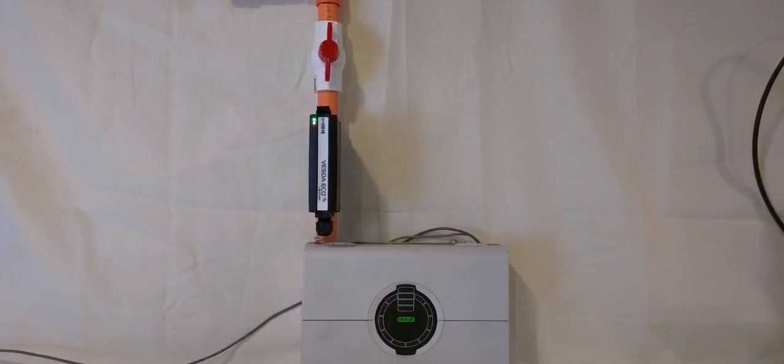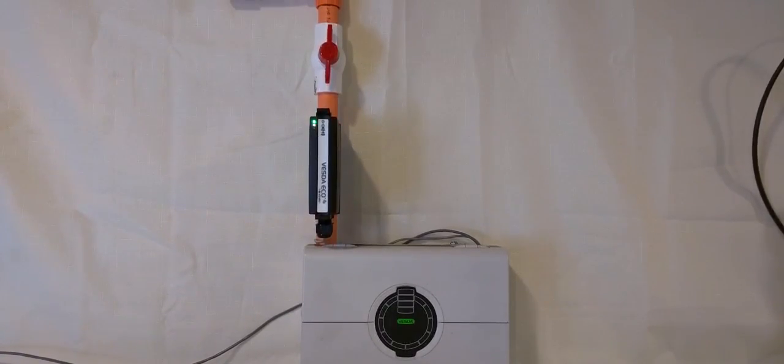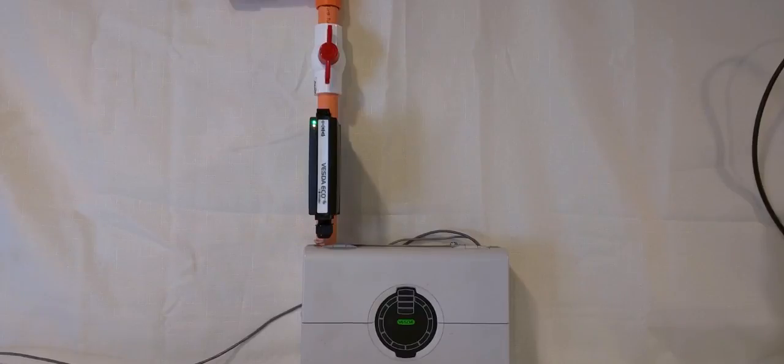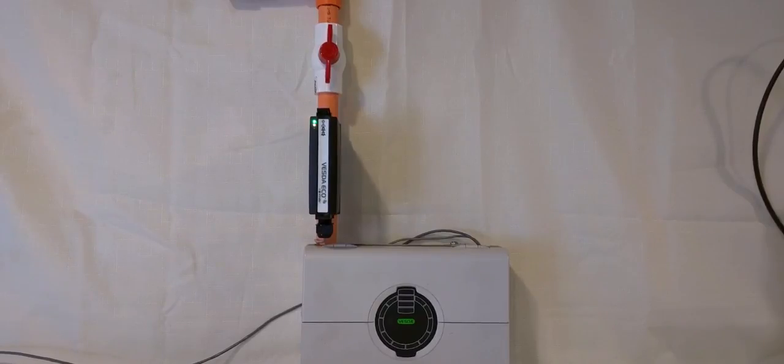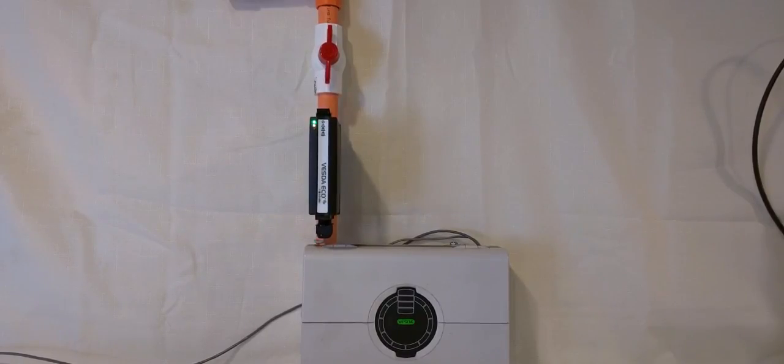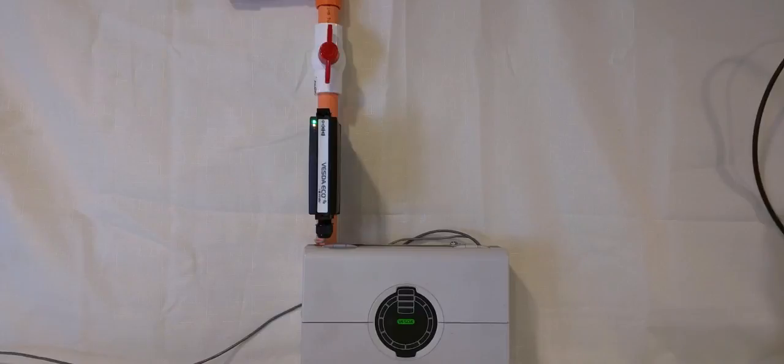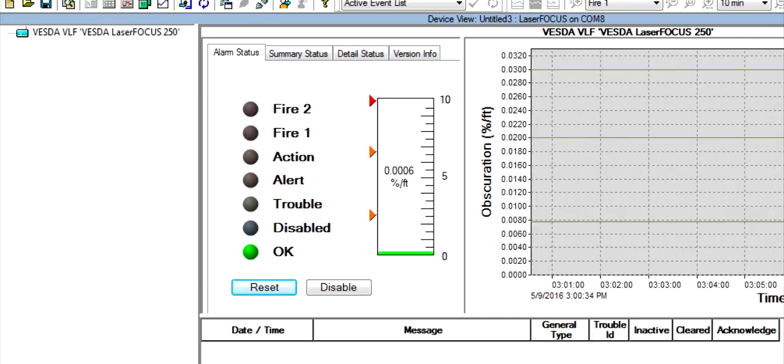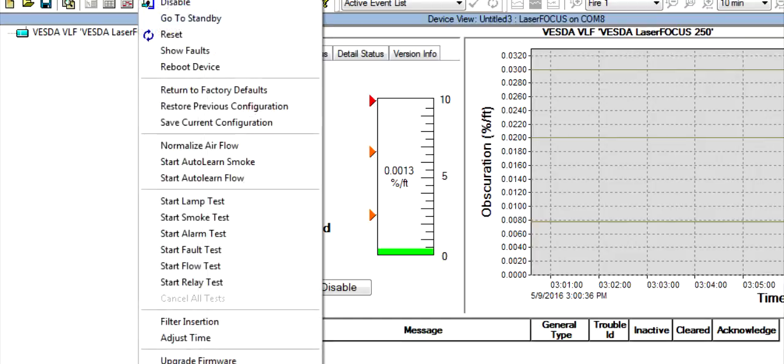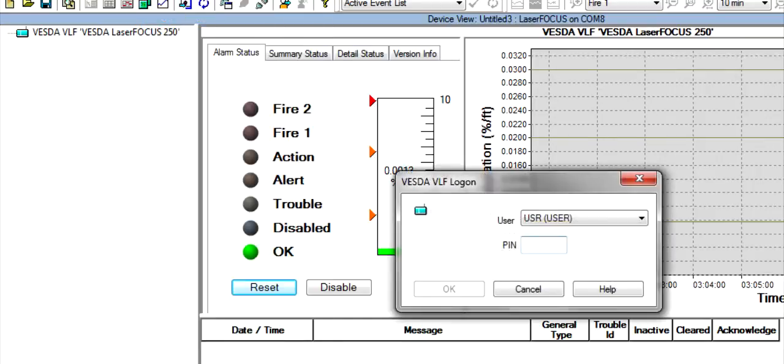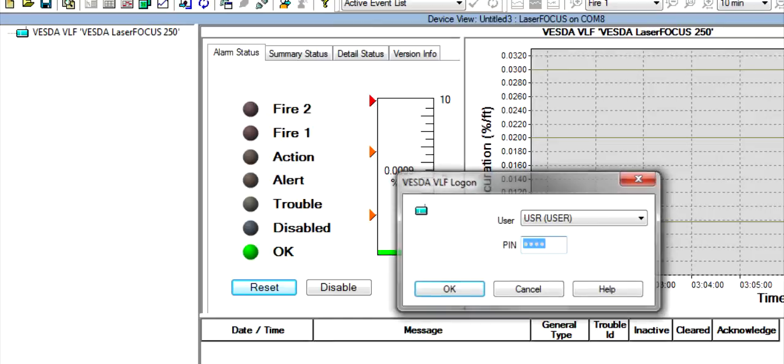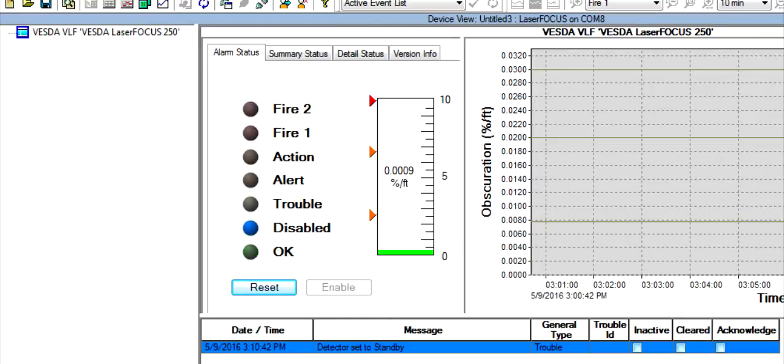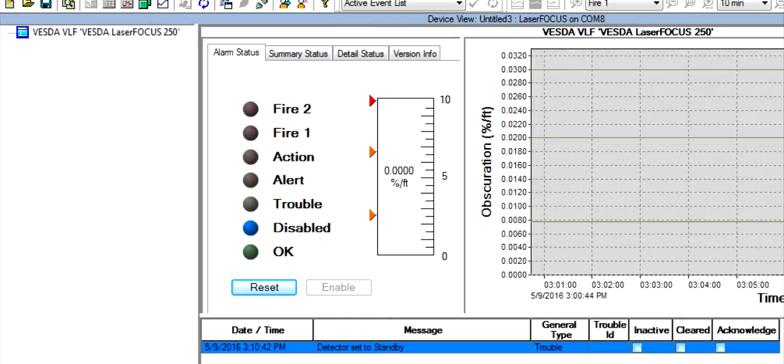The first step is to disable the VESDA detector. This can be done by logging into the VESDA with the VSC software. Once you log into the VESDA, go to Device, go to Standby, enter the user pin 111, enter OK. The device now is in standby and the aspirator will stop.